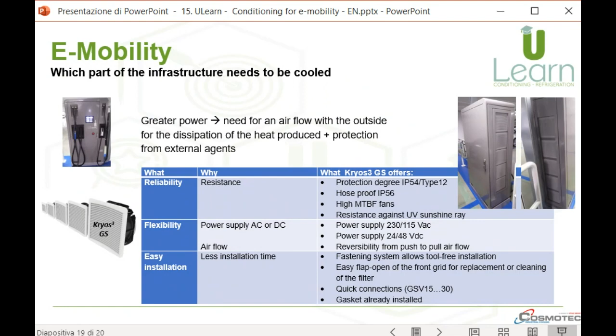At the end, more installations power directly on the charging column, which can require an airflow with the external in order to dissipate the internal heat load, offering at the same time a suitable protection against external agents. For cooling of the column that we can call high power for fast charging, the solution is the filter fan Krios 3, when the ambient temperature is lower than the required internal temperature. Thanks to its reduced depth, they are installable on several columns. Moreover, they offer reliability with certified protection degree and high MTBF, flexibility and easy installation.